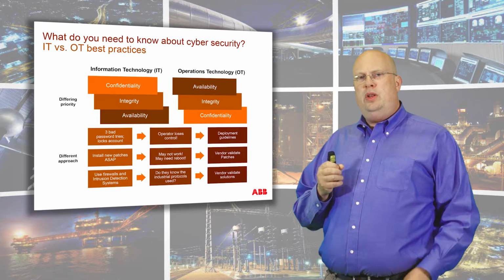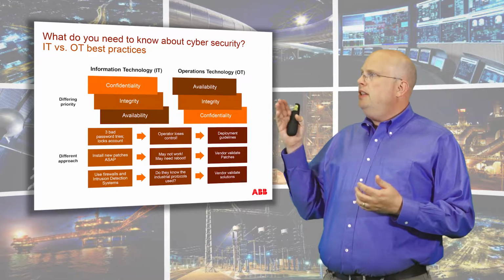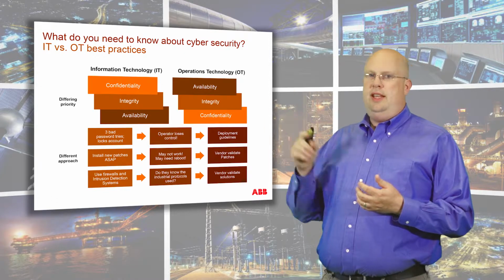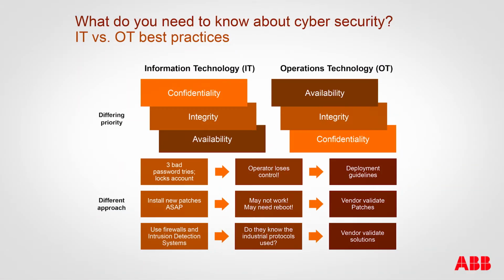Another important thing to know when you start with cybersecurity is there is a difference between IT and OT. IT is information technology, OT would be operational technology. And the IT folks, they are really, really concerned about confidentiality. How do I protect my data? I don't want credit card information to go out or medical records or anything like that. I want to protect that data at all cost. So with that being their foremost protected thing, they are willing to let go of the availability. They will shut down a system if there's a risk to the data.